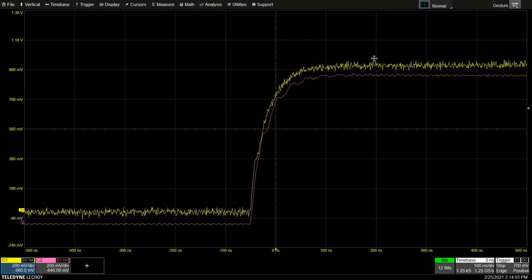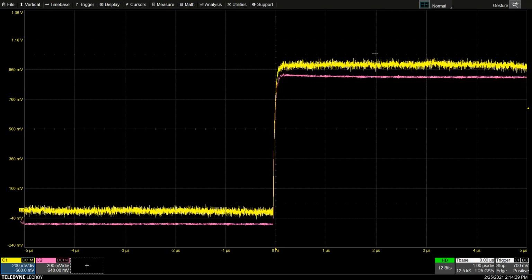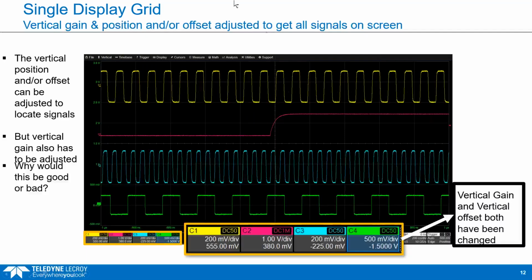So not only, my point is, is amplitude accuracy affected by the acquisition of low amplitude waveforms, timing makes a big difference as well. I think that describes that. And let's go back to our slide set to show you that. So there we go.